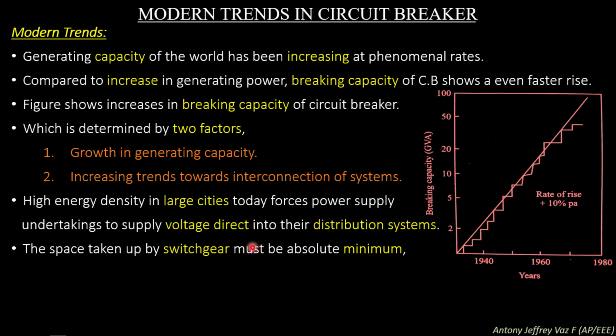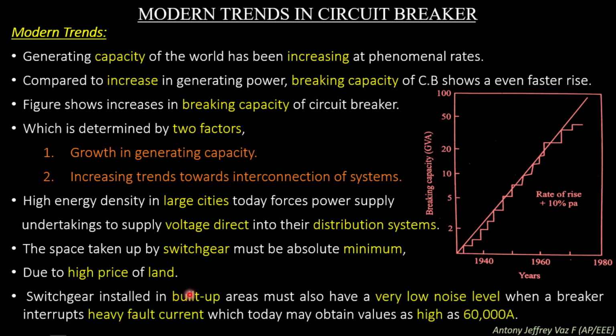The space taken up by switchgear must be an absolute minimum due to the high price of land. So when a switchgear is installed in a user's premises, it should take a minimum amount of space, because in cities the price of land is very high. Switchgear installed in built-up areas must also have a very low noise level when a breaker interrupts heavy fault current, which today may reach values as high as 60,000 amperes.